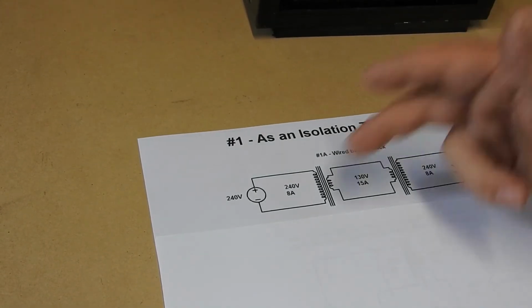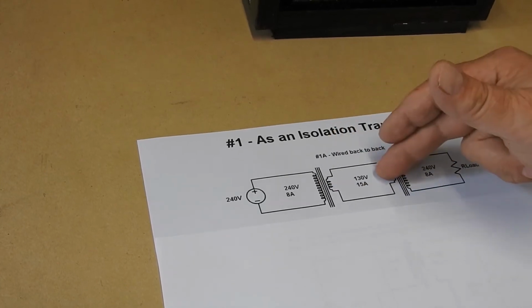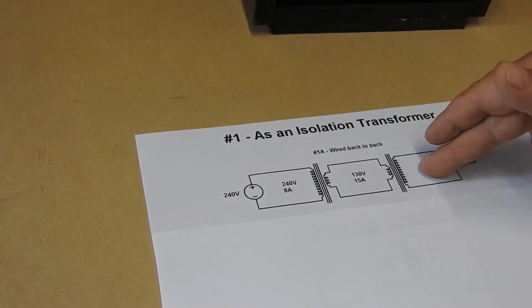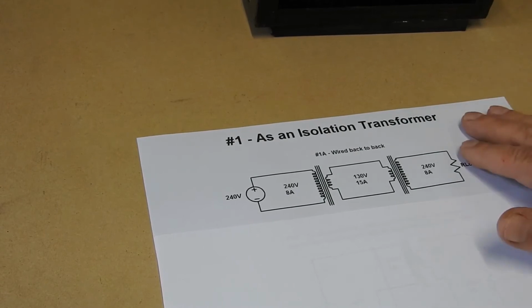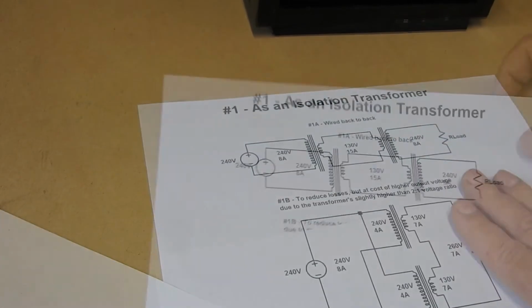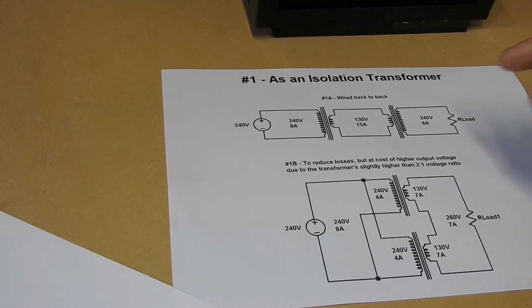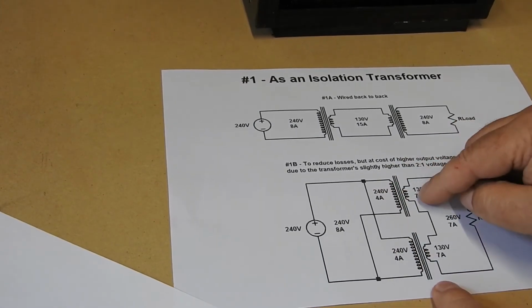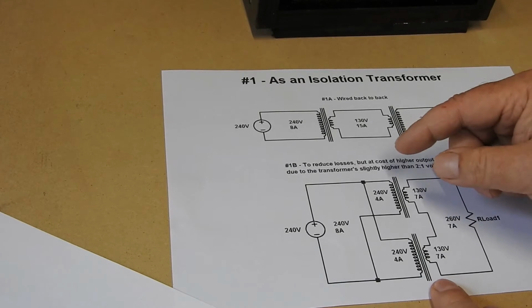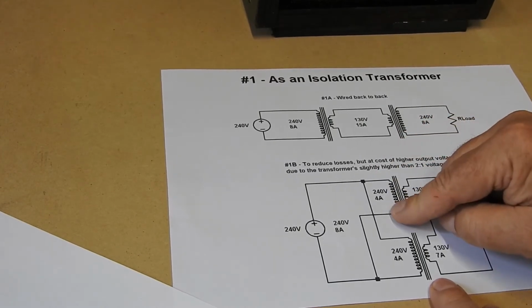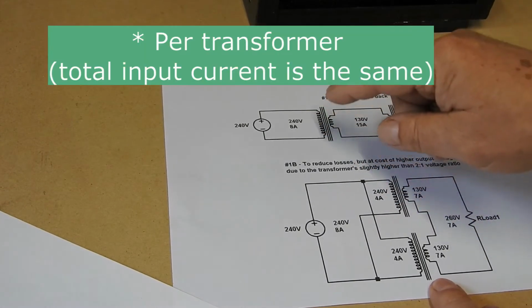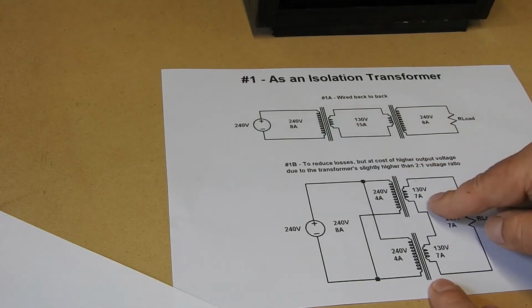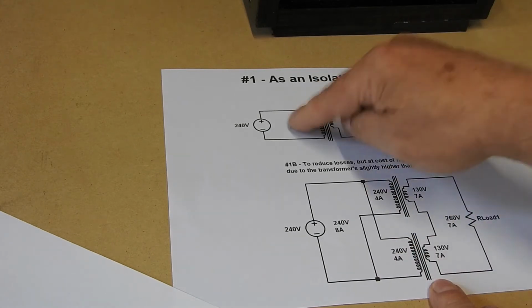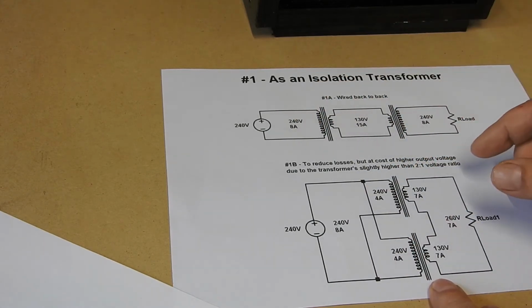Now, this is what I did in the recent video of an isolation transformer. 2 of them wired back to back, the 2 secondaries connected together, input on one primary, output on the other. And there's a better way of doing that, which is this. Put the 2 primaries in parallel and the 2 secondaries in series. That way you've only got half the current going from 4 amps to 8 amps, going from 8 amps to 4 amps, so half the primary current, and only 1 level of magnetic coupling instead of 2. So you'd expect less voltage sag.